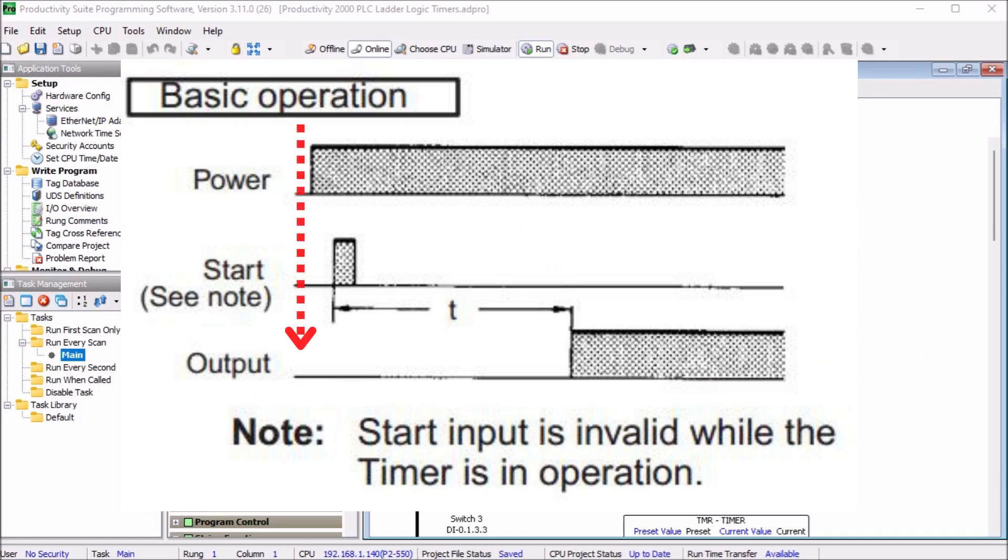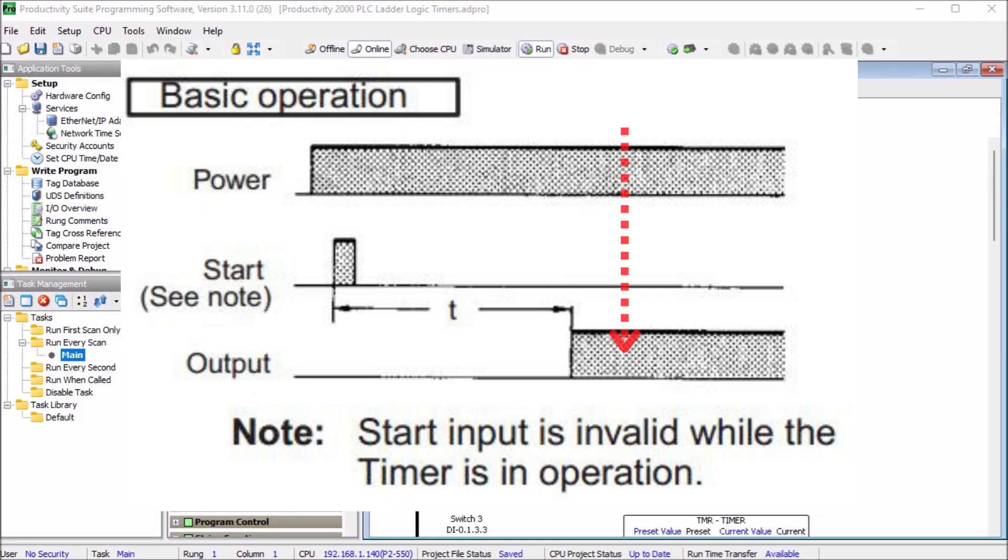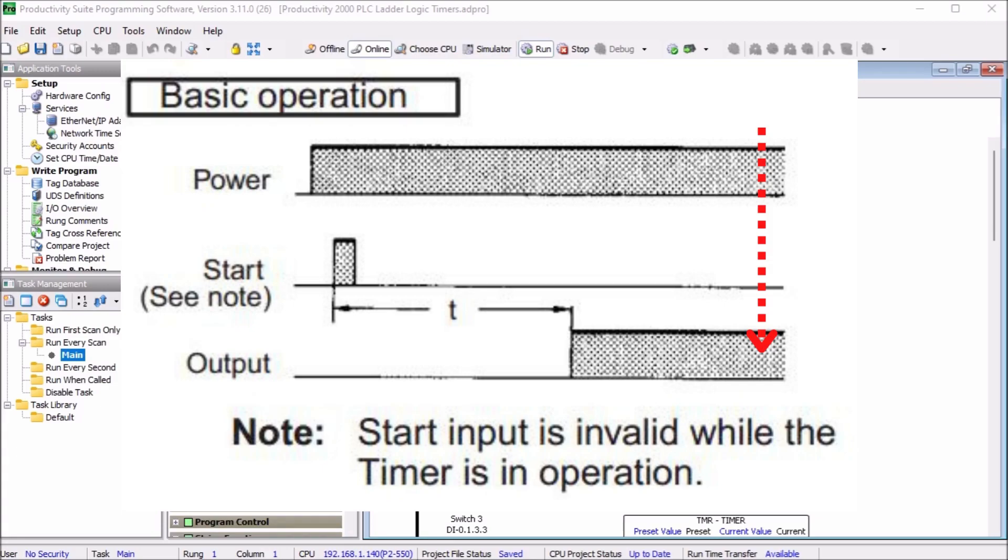In this timing diagram, the output is off when power is off. When power is on and a momentary start signal is received, a timer starts timing. At the end of the time duration, the output is turned on as long as the power remains on. If the power turns off, then the output also turns off. As you can see, it is visually easier to see the timing chart than just reading how it works.